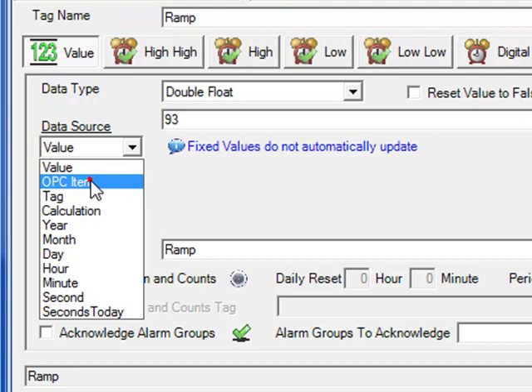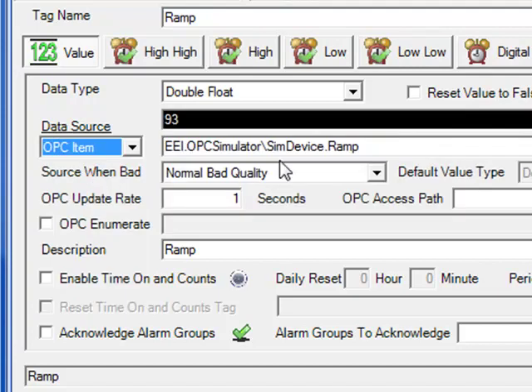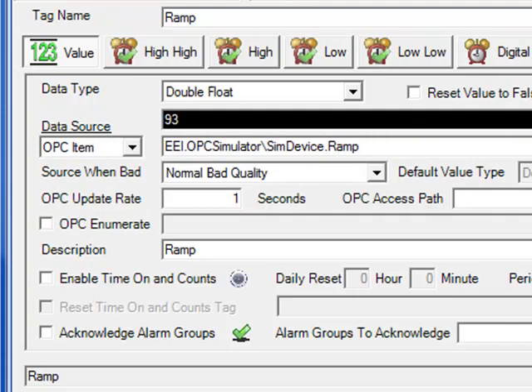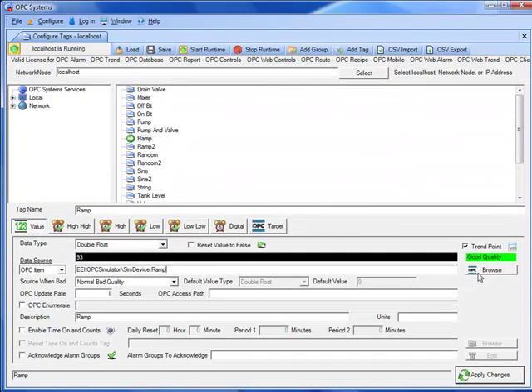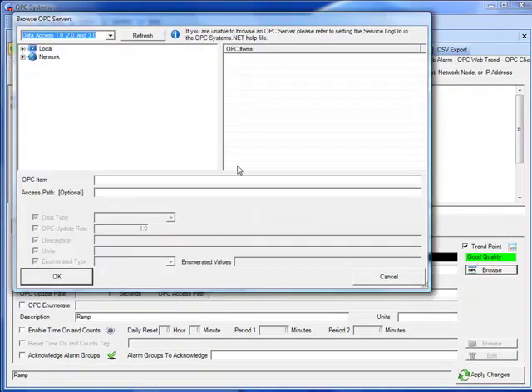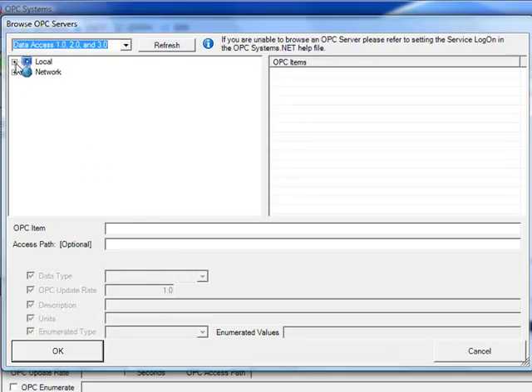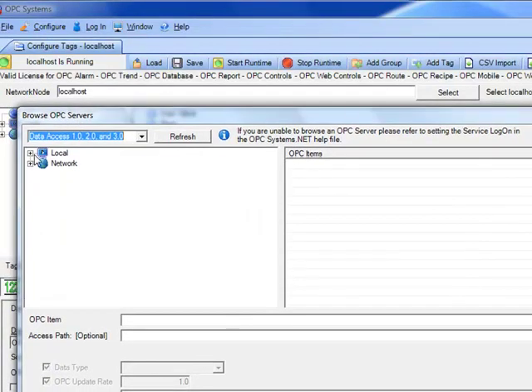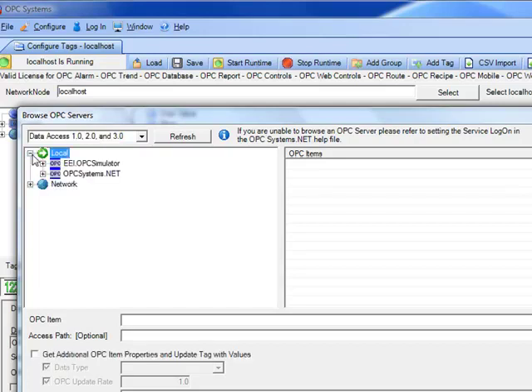One of the most commonly used data sources is an OPC item. This allows you to connect to an OPC server, whether locally or remotely. When you choose OPC item as a data source, there's a browse button to the right. When you select this button, another dialog appears which you can use to browse your OPC servers. Even if your service is connected over a remote system, you can choose local and you would be browsing OPC servers on that remote system using a TCP connection, eliminating the DCOM connection.